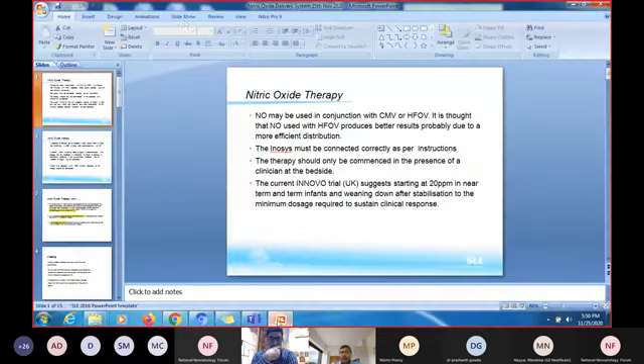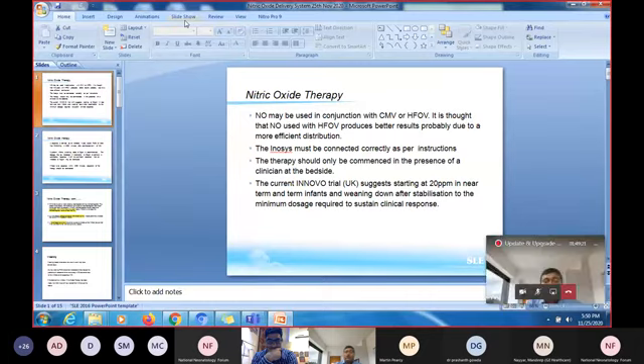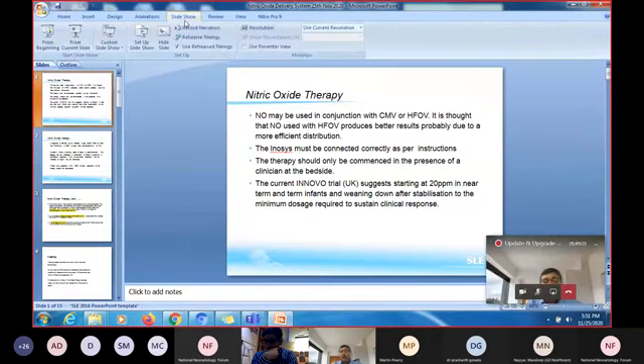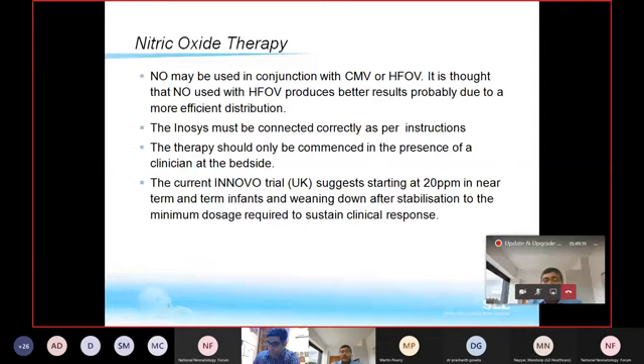For term babies and mostly near-term infants, what we have seen is that up to 20 ppm is recommended. And for the preterm, we talk about starting with 5 ppm and then trying to increase up to 20 ppm. Then, if you don't get a result, you try to increase to a maximum of 40 ppm. If you don't get any results within 15 to 30 minutes, then you can stop the therapy. That is what is recommended.